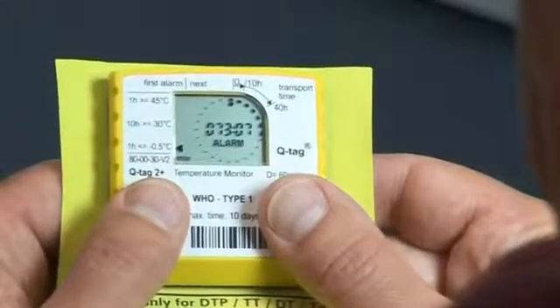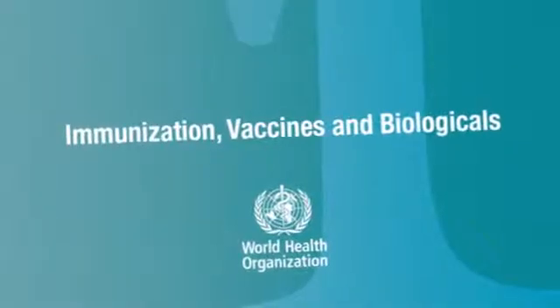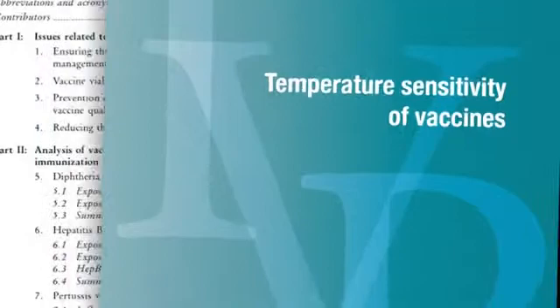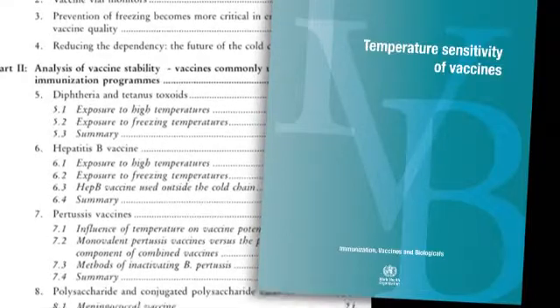The appropriate control of temperatures during the storage and transport of vaccines is critical to ensure potency and safety. Liquid formulations of vaccines containing diphtheria, pertussis, tetanus, hepatitis B, hemophilus influenzae type B and their combinations — adsorbed vaccines — should not be frozen.